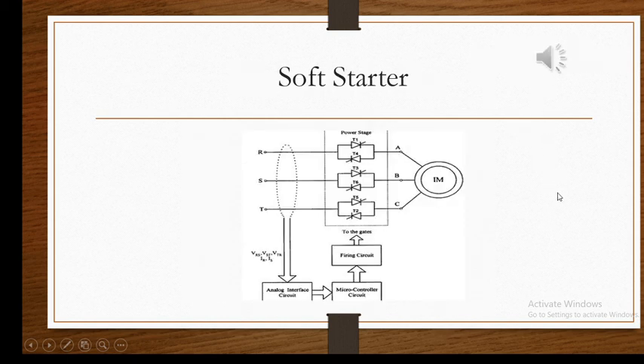In case of a soft starter, in between each phase of the input supply and the motor, a triac is incorporated. A triac is a powerful semiconductor device which consists of two thyristors. The advantage of having a triac here is that by applying pulse on the gate of a triac, we can control the current flowing through it. So with the help of a PWM generator, we can control through triac the current that is flowing from the supply to the induction motor, and hence by allowing the current to increase gradually, we can avoid the large inrush current that the motor would have to suffer otherwise.